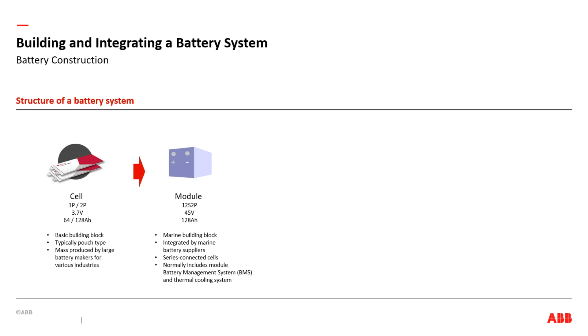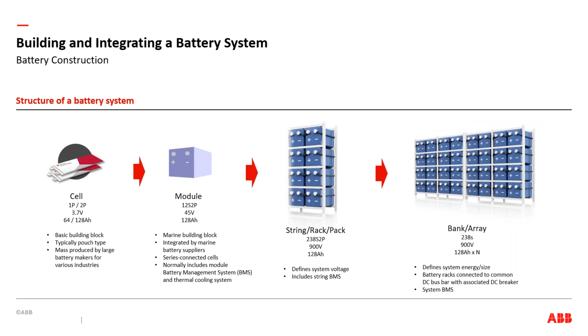The string defines the vessel's system voltage. In this example, we put 20 of these 45 volt modules in series to get 900 volts total on our system. That becomes the smallest building block of energy you can add to the vessel, since you add them in increments of 900 volts apiece. Finally, you stack a number of those strings together into a bank or array, which defines the total amount of energy storage on the vessel. So everything from the cell up to the bank level is integrated and provided by the battery producer.